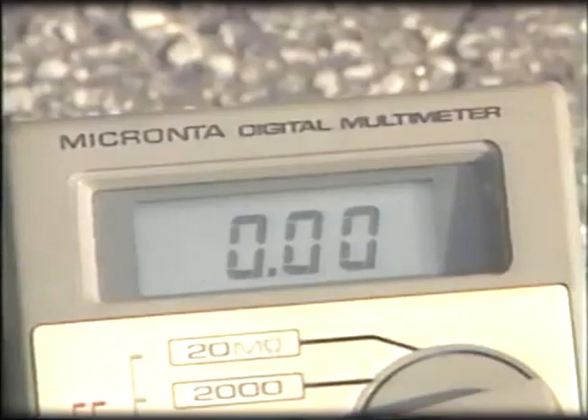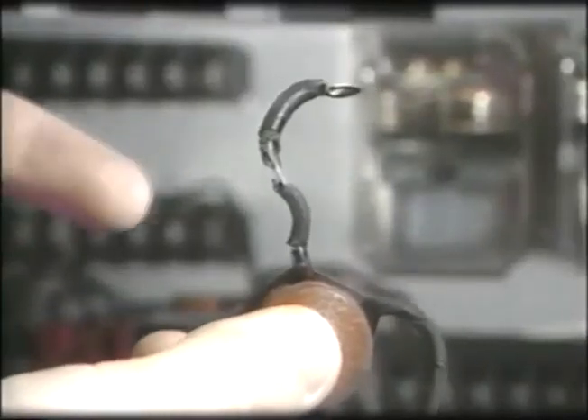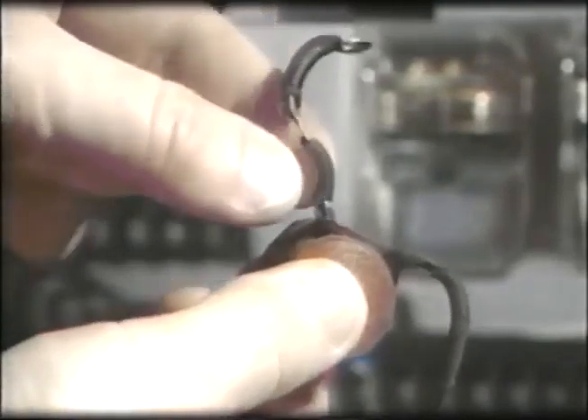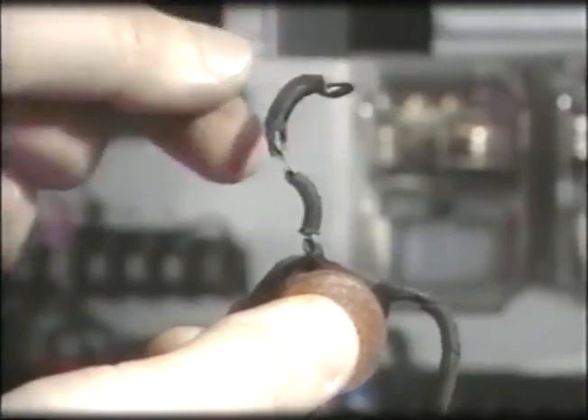Normal wear and tear is the second category. Look for corrosion, particularly in bonds at cabinet connections, ground wires, and arrestor leads. Use your ohmmeter to check for electrical continuity across corroded joints. Corrosion will be obvious. You may have to search harder for broken wire, especially in arrestor leads. Make sure that all ground wires are unbroken and connected.